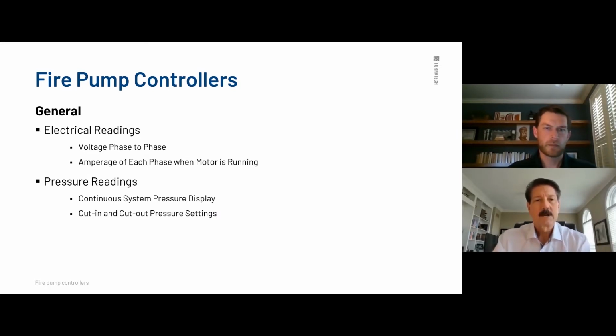Electrical ratings. Fire pump controllers, electric, are pretty easy. All you really have to do is look at voltage and horsepower. So the electrical readings that you'll see on these controllers are required on the front screen or on the front of the enclosure itself. You need to know what the voltage is phase to phase. You need to know what the amperage is phase to phase, and if the motor's running. These are all requirements by code.